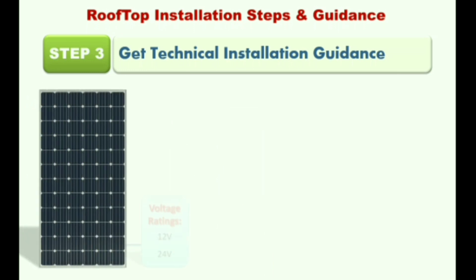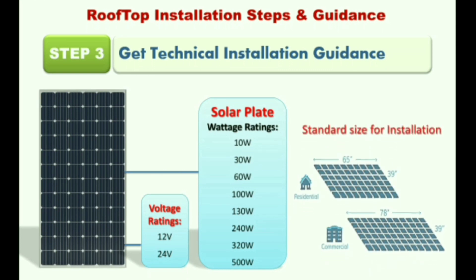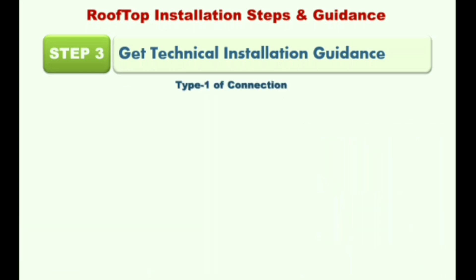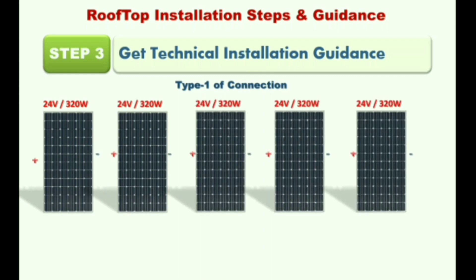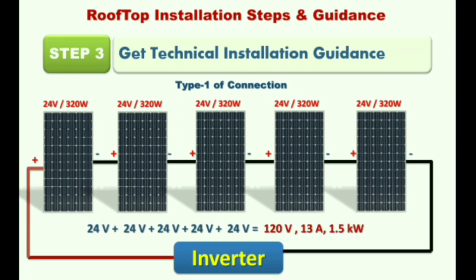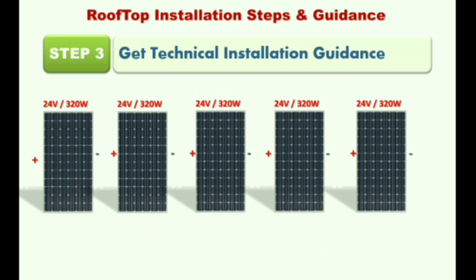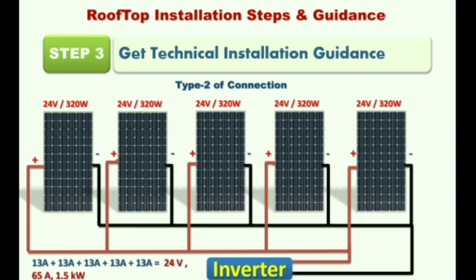Solar panels are also available in different voltage and power ratings, as shown in the images. For panel connections: in a series connection, all plates are connected in series, giving the plant a rating of 120V, 13A, 1.5 kW. In a parallel connection, all plates are connected in parallel, giving an overall plant capacity of 24V, 65A, 1.5 kW.